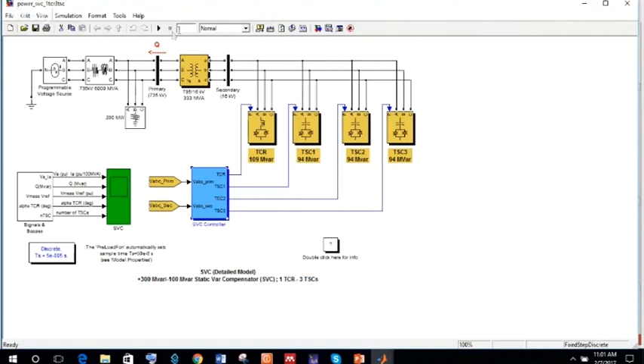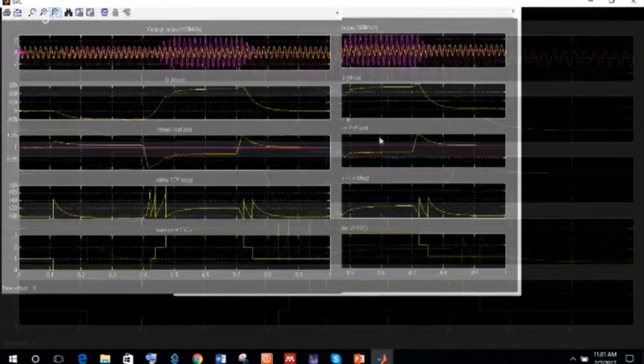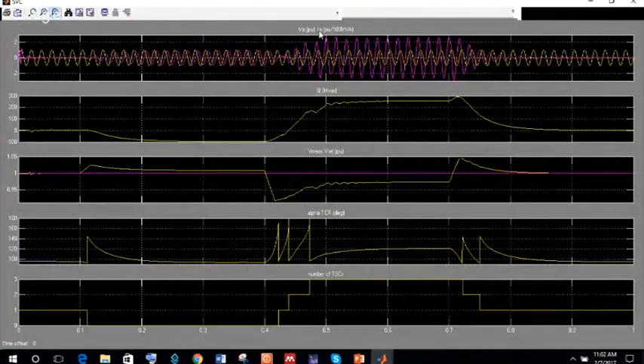Okay. Now, once we enter these values, the remaining values like transmission line parameters, that all you know, must be entered. This is the diagram showing primary voltage, current, and reactive power that is supplied. Since we are operating in voltage regulation, we have the measured value and reference value. This is the angle, because for the thyristor controlled reactor, the reactance is controlled by the firing angle, that is alpha, and the number of thyristor switched capacitors. You know that capacitor banks are either switched on or switched off.